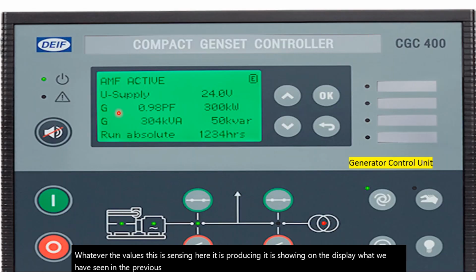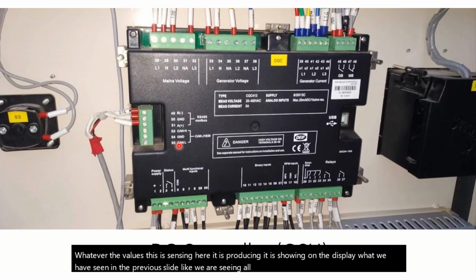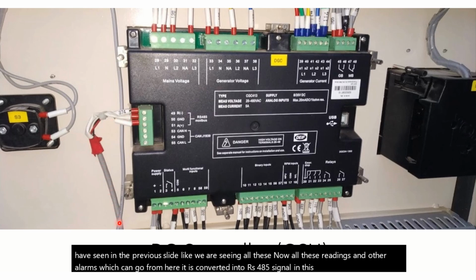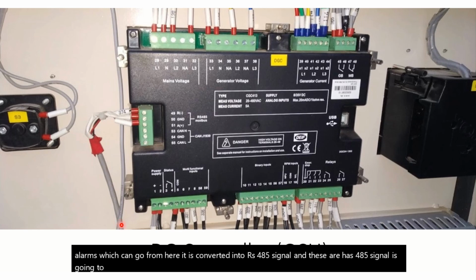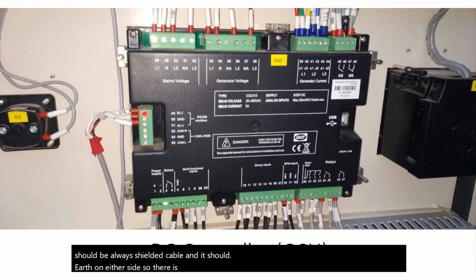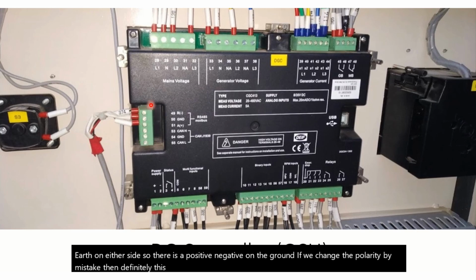Like we are seeing all these readings and other alarms, which can go from here. It is converted into an RS485 signal, and this RS485 signal goes to our server, and from there it goes to the central monitoring system. This cable should always be a shielded cable and it should be earthed on either side. So there is a positive, negative and a ground.